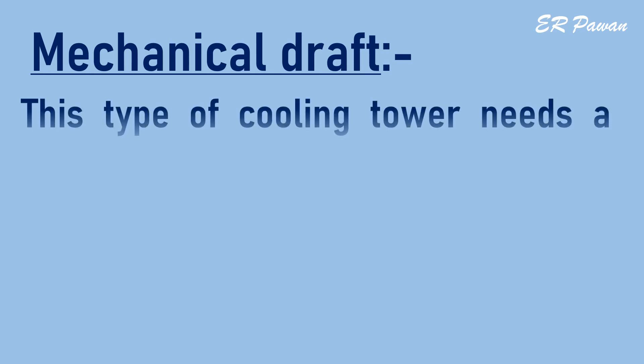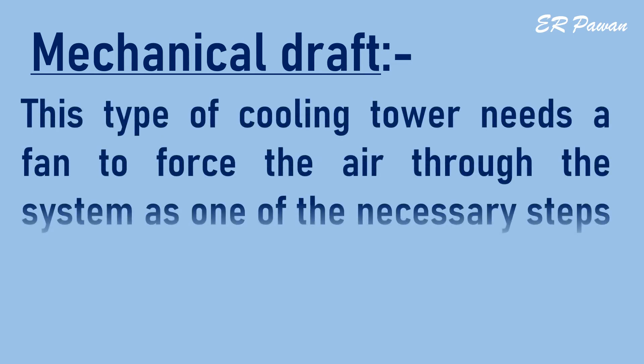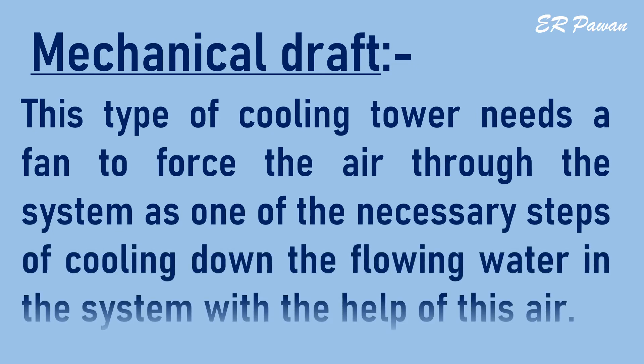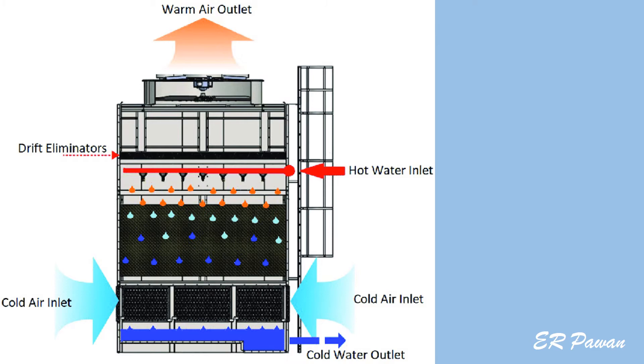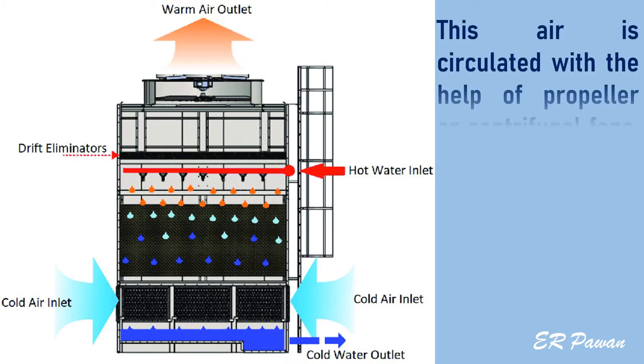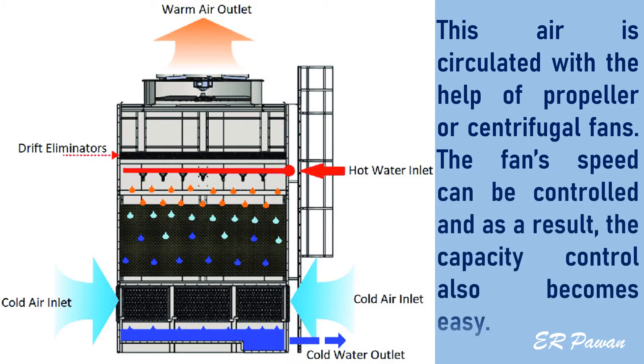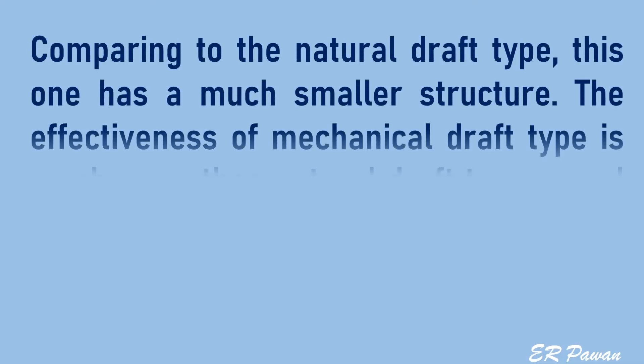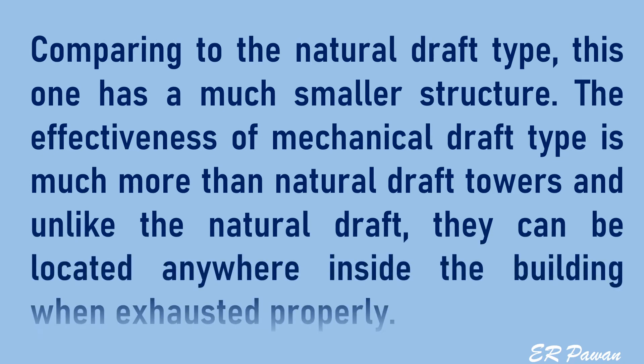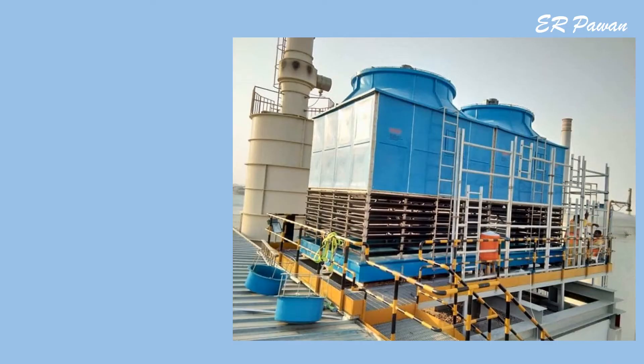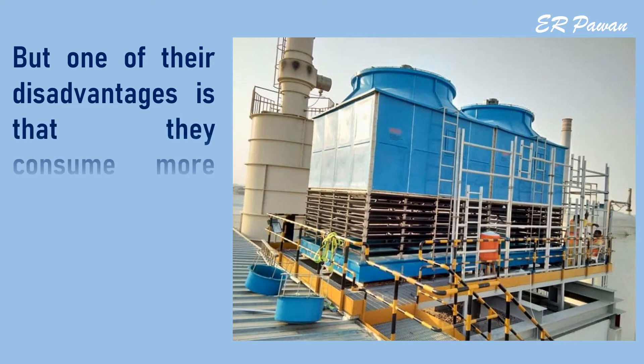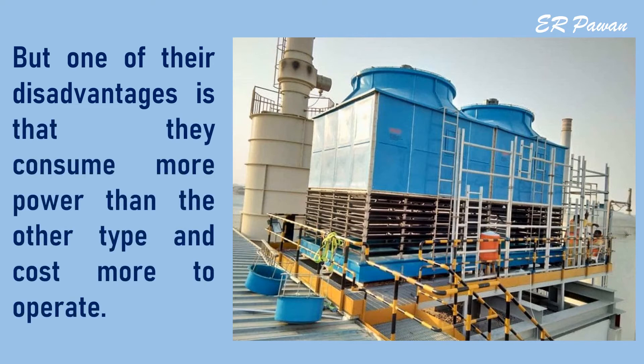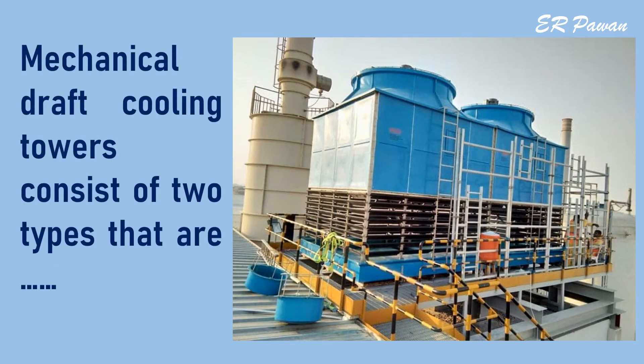Mechanical draft: this type of cooling tower needs a fan to force the air through the system to cool down the flowing water. Air is circulated with the help of propeller or centrifugal fans. The fan speed can be controlled, making capacity control easy. Compared to the natural draft type, this one has a much smaller structure. Mechanical draft towers are more effective than natural draft towers and can be located anywhere inside the building when properly exhausted, but they consume more power and cost more to operate.